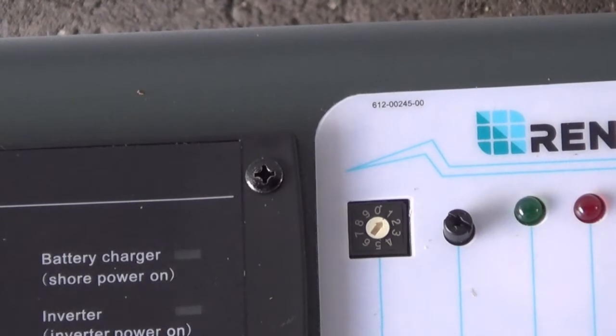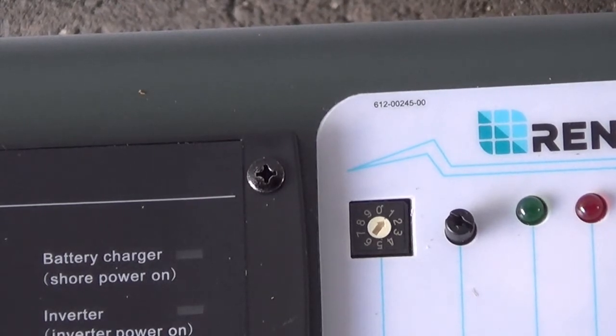So that's pretty cool. One feature that's pretty neat is this little dial we're looking at right there. It's a selector switch that allows you to tell the unit what kind of batteries you're using, so then it will know exactly what kind of voltage to put out to it. You can choose between gel, AGM, sealed lead acid, flooded lead acid. There's a couple more, so pretty nifty.